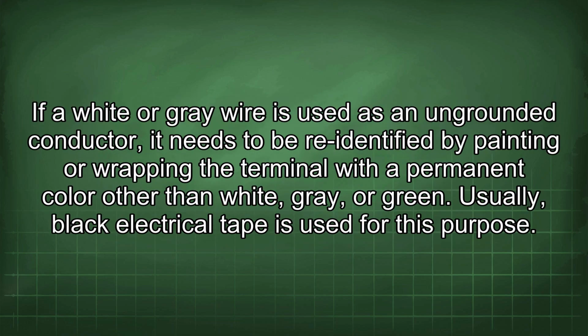If a white or grey wire is used as an ungrounded conductor, it needs to be re-identified by painting or wrapping the terminal with a permanent color other than white, grey, or green. Usually black electrical tape is used for this purpose.